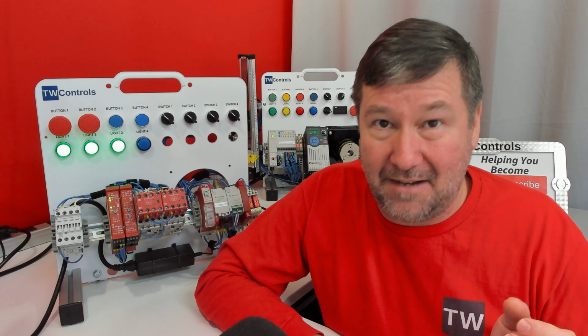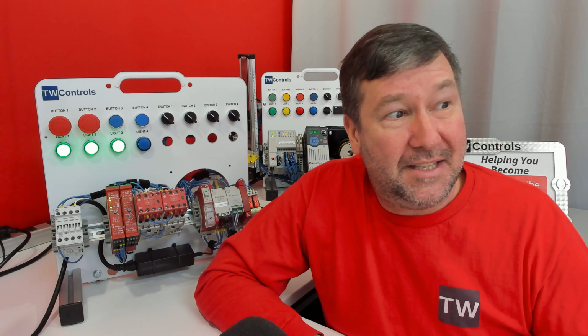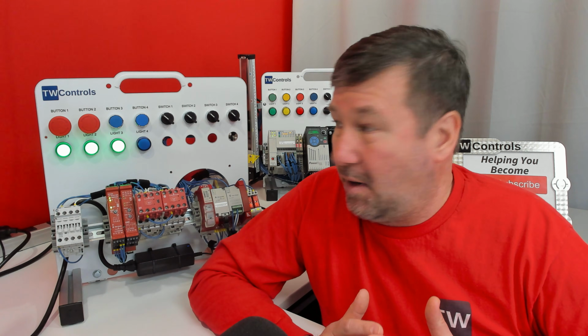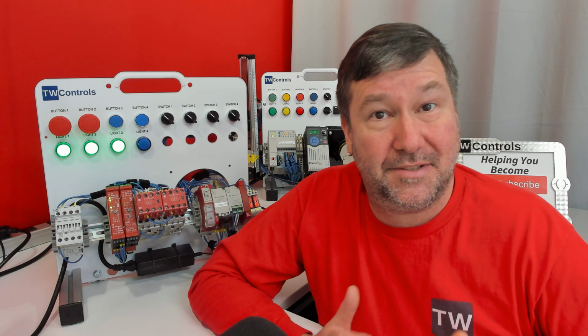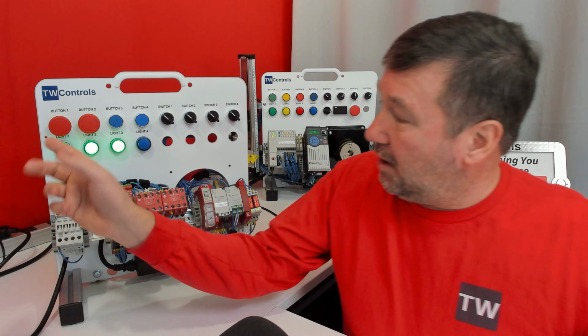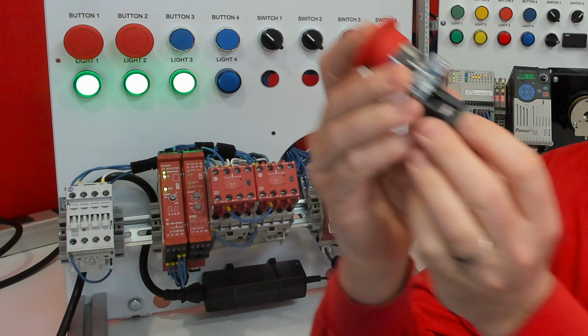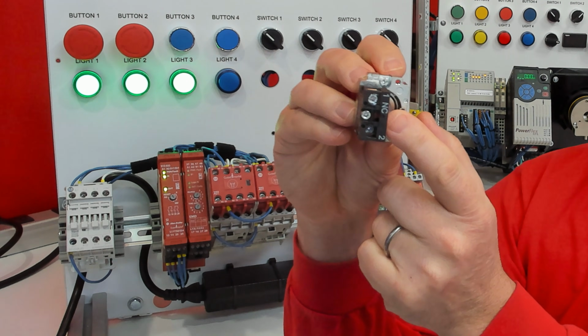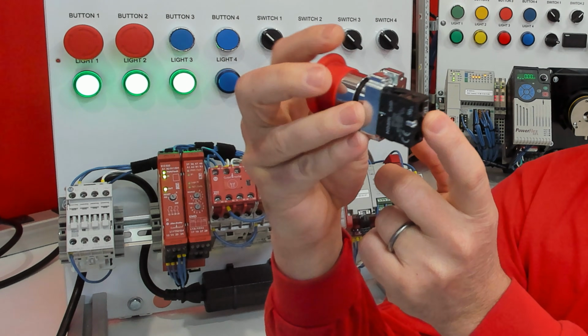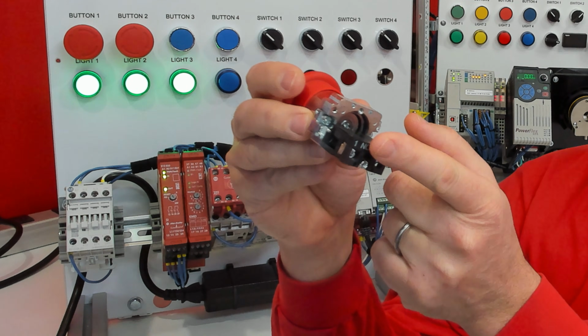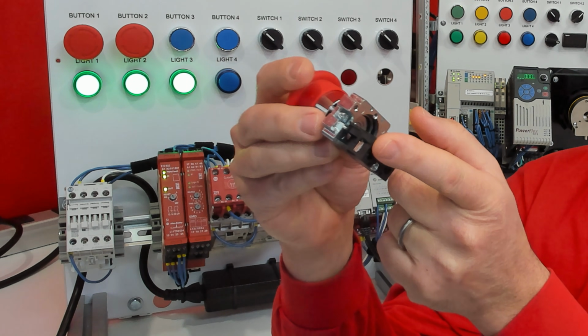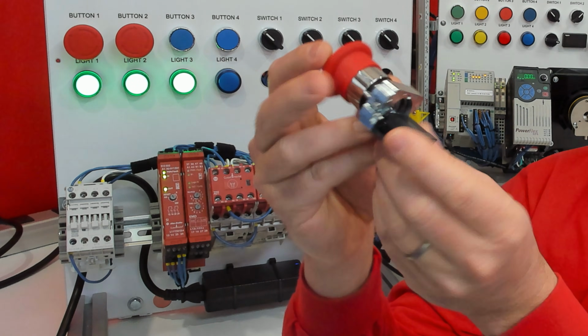Now, one easy way to eliminate failures is more robust equipment. And it could be as simple as that. If you have something that has a really common failure, then simply changing that out could be good enough. But another really often used way of eliminating these hazards is redundancy. So on our basic MCR, you would have an E-stop with a single contact, normally closed, something like this. Also, a lot of times you may see a normally open on these. That is not redundancy. Usually that's going to some type of light to tell you it's pressed.